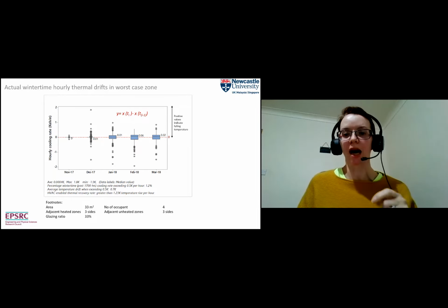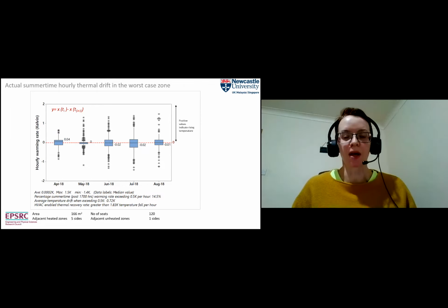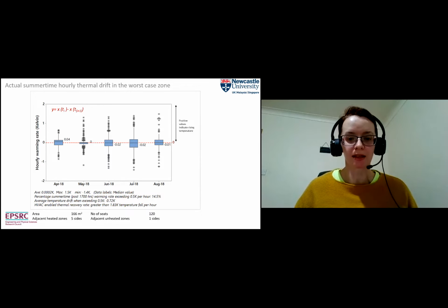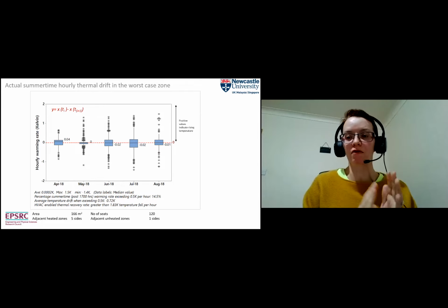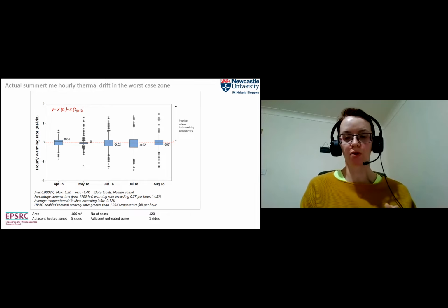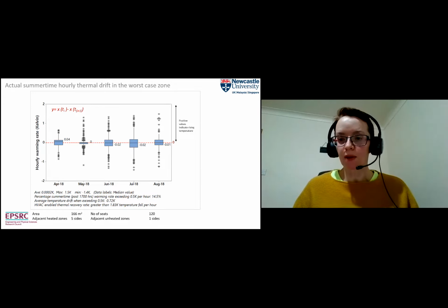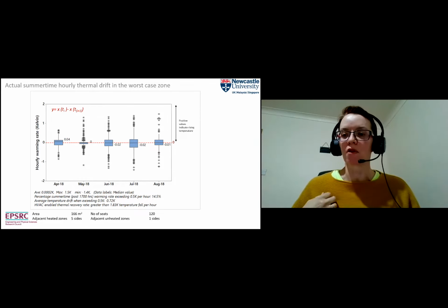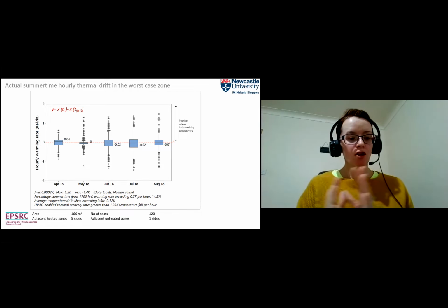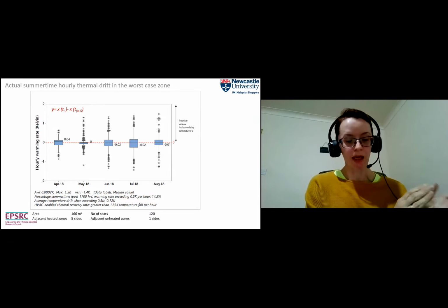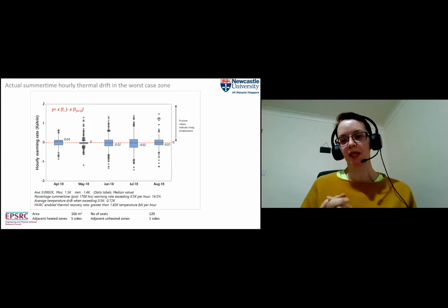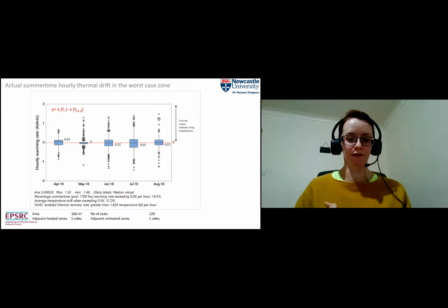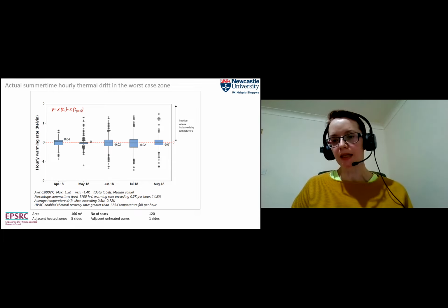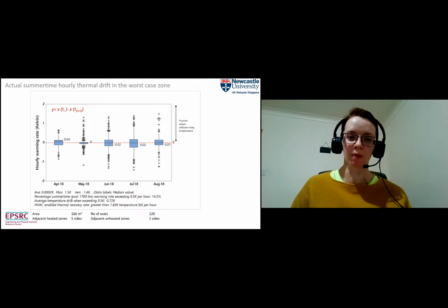We also did the same thing looking at what happens if we turned it off in summer and stopped the cooling: how quickly would it warm up? This is the summertime thermal drift in our worst performing space. We again want the temperature to change no more than 0.5 degrees per hour. We looked at the months April through to August, and found that for that period more than 14% of the hours were experiencing a warming up more rapid than that. So whilst people might not notice so much if the heat pumps were off in winter for a short period, they would notice more often if we turned the cooling off in summer for a period. So our building is doing slightly better in terms of heating than in terms of cooling response.